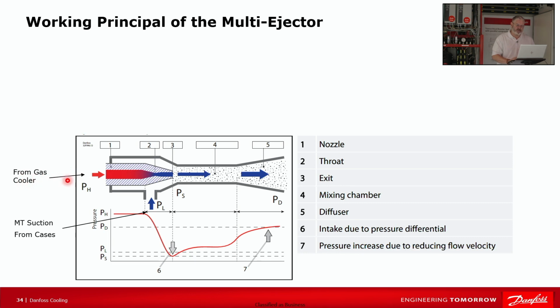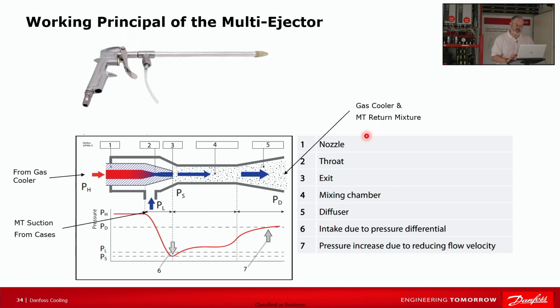So entering the actual ejector itself, the device we just looked at, we've got the mass flow from the gas cooler. We've got the medium temp from the suction cases coming in the little, looks like a revolver barrel portion. And then those mix together and they exit and return to the flash tank. So for me, this kind of reminds me of a wand for a pressure washer. A pressure washer wand does the exact same thing using a Venturi effect, which is kind of what we're creating here.